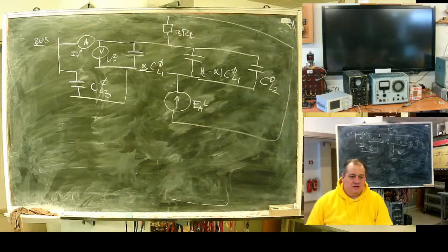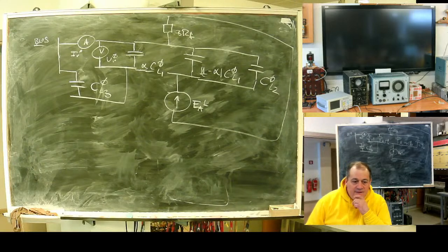Nothing changes. Absolutely nothing. Yes, absolutely nothing. Current through relay is really zero, it depends from fault place along line. Do you understand what it means for you as protection engineer? You need to disconnect faulted line.